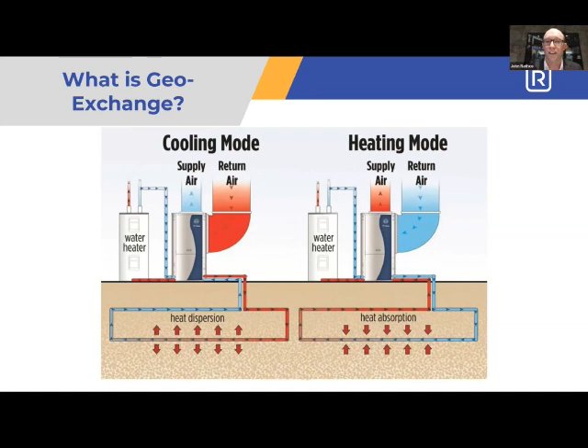So in a geoexchange system, you need heat in the winter. We take that heat out of the ground, putting a cold plate touching the water coming from the ground to absorb that heat, and push it into a hot plate inside your building. Then we simply reverse that process in the summer: we take all the heat your building is absorbing from the sun and the people inside it, absorb that in a cold plate in your building, then upgrade that heat and pump it into a hot plate that deposits it beneath your building in a massive geoexchange bore field system. That's geoexchange 101.